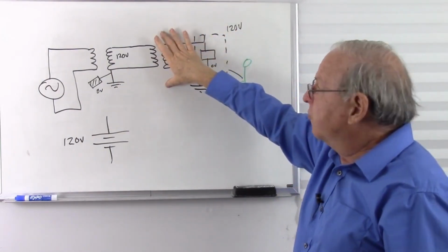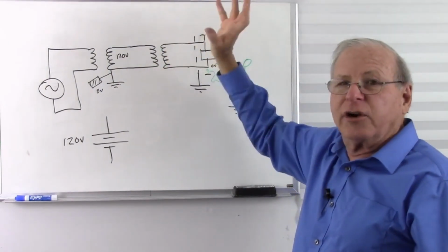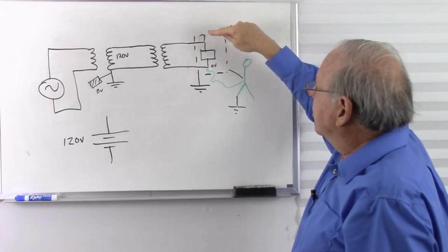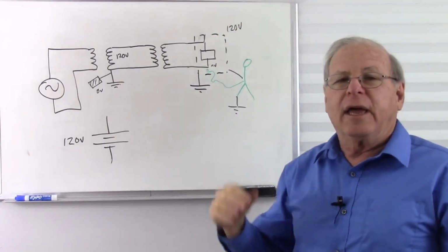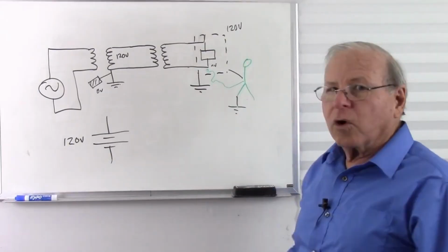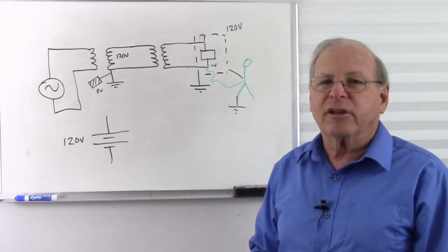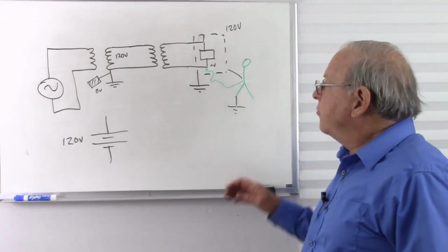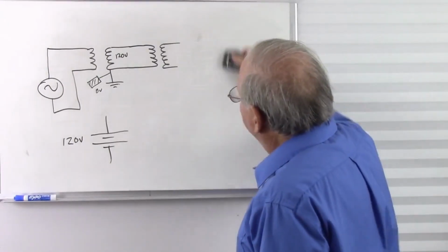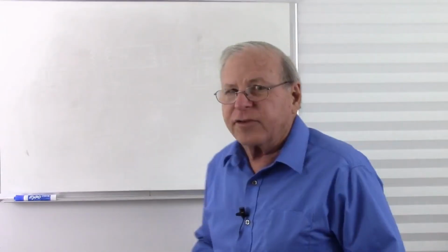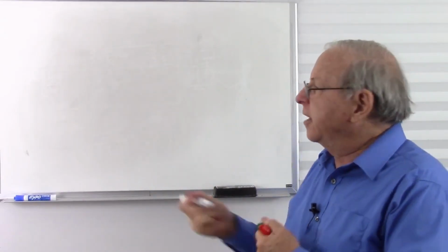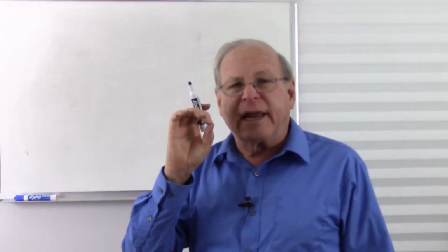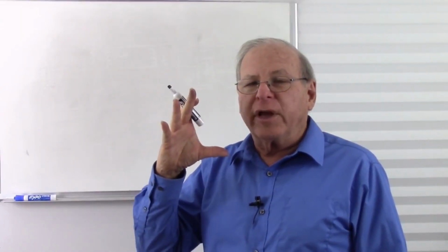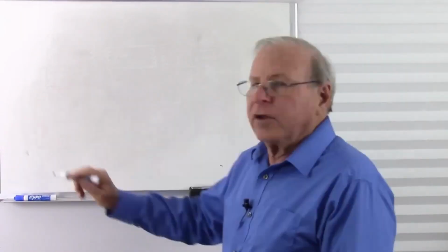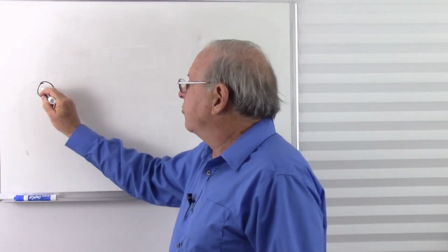With the isolation transformer, it's isolated. It's like a generator just hanging in the air. I have to touch both sides to get a circuit. So one more layer of protection by using an isolation transformer. Now, another place you might use an isolation transformer, this might be kind of rare, but I've used it this way, is as a protection against a direct connection to the mains when you are testing something and you don't know if it's going to be a short circuit or not. So here's my mains connection. There's my connection to the wall here.